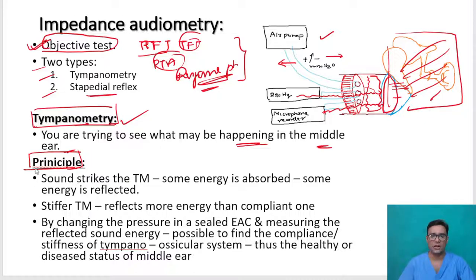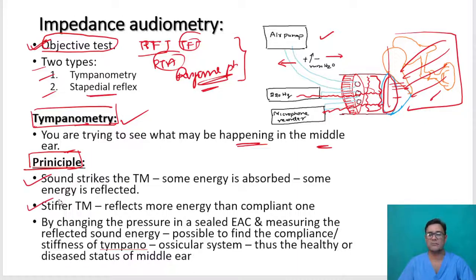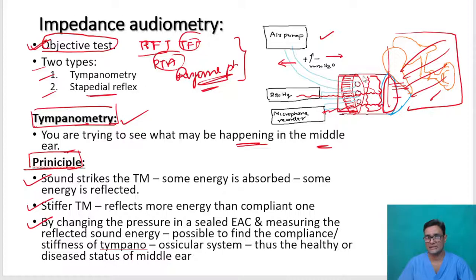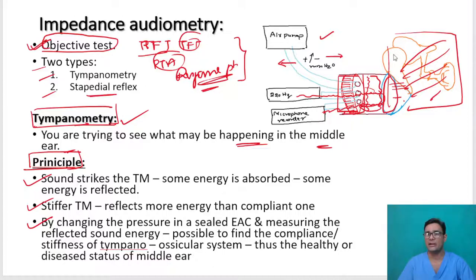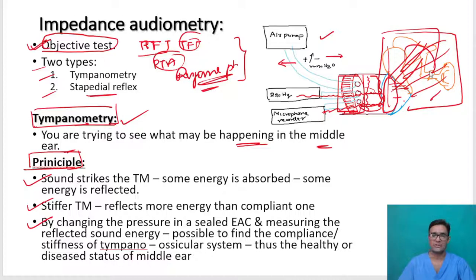This is the basic principle. Sound strikes the tympanic membrane — some energy is absorbed, some is reflected. A stiffer tympanic membrane will reflect more sound energy. By changing the pressure in a sealed external auditory canal and measuring how much energy is reflected back, we can get an idea about what is happening in the middle ear — that is the tympano-ossicular system.